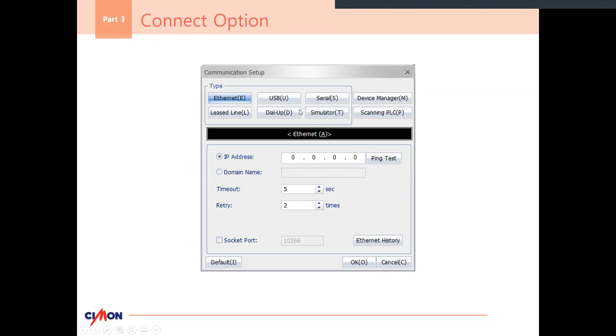When you want to download a project onto your PLC, I recommend either using download, PC to PLC - you won't be able to monitor your device, but if you're in a hurry or already know something's going to work, you can just download it that way. If you want to monitor what's going on, look up here a little higher, it says link, download, and monitor. This commits to the download but makes sure you had correct communication, and you'll be able to see what your actual registers are doing in real time. That's a nice feature we'll be utilizing with the simulator today, so you'll get some exposure to that.